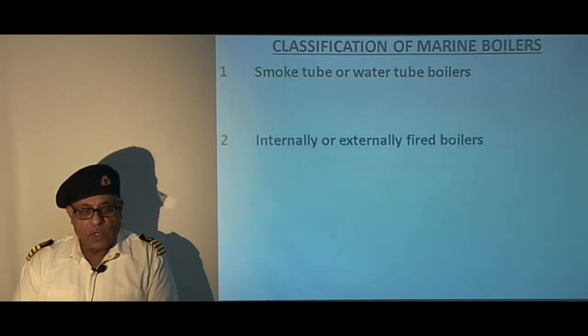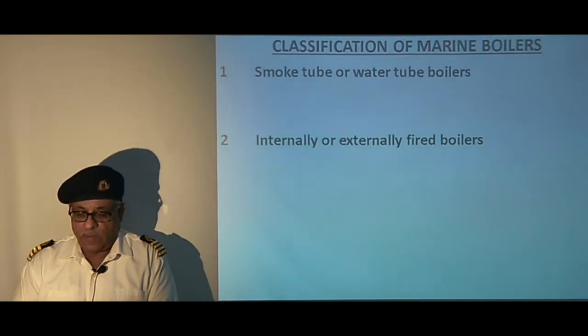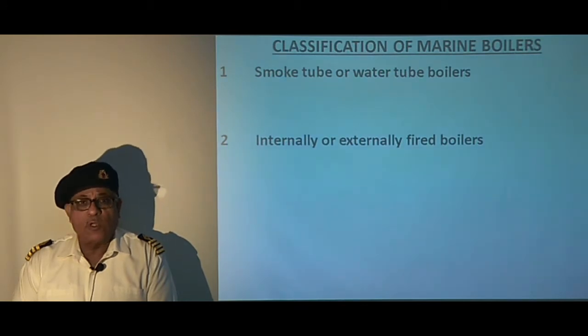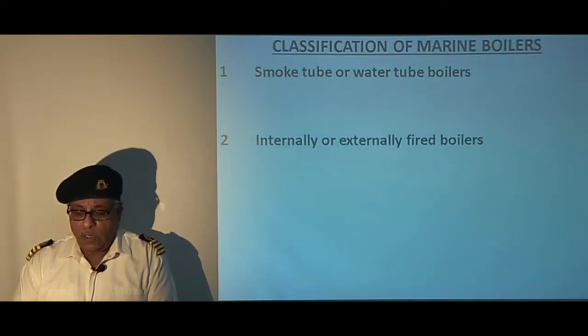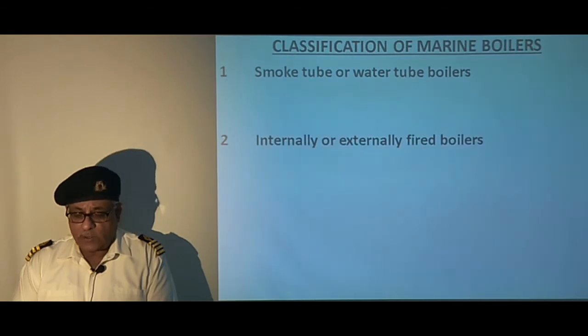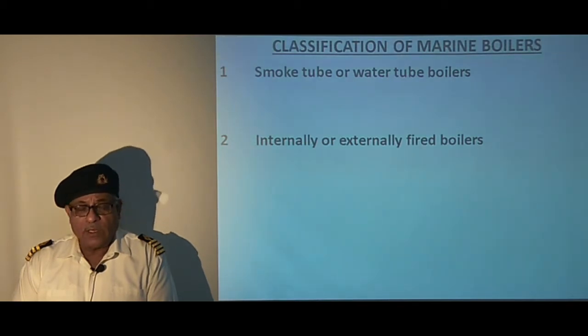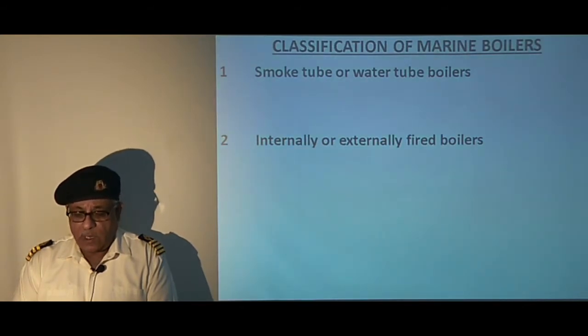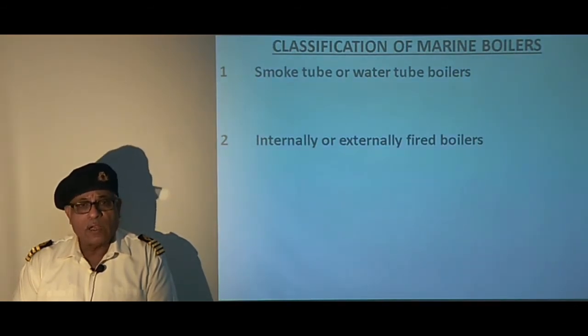The second classification is internally or externally fired boilers. Internally fired boilers have a furnace in which the fuel is burnt to heat up the water — most boilers fall into this category. However, exhaust gas boilers on motor vessels, which use the waste heat of engine exhaust, fall into the category of externally fired boilers. Steam ships are equipped with oil fired boilers whereas motor vessels, in addition to the oil fired boiler, may also have an exhaust gas boiler, a composite boiler, or both.